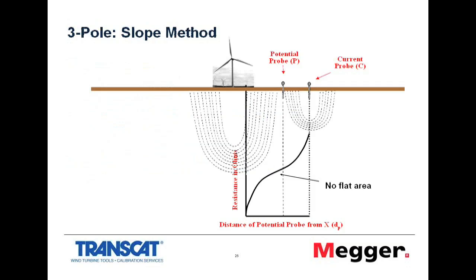If I look at a single wind turbine, I can see that the sort of spacing I would require is going to be in the order of something like 425 feet. A 2 megawatt turbine earth system is approximately, across the biggest dimension of the earth system, 75 foot across. And with that kind of size earth system, I need to have the current probe about 425 feet away to be able to see a flat. That's taking into account variation in the soil makeup and the moisture content, which can vary throughout the year, and we have to take into account those factors when we take that measurement. Effectively, you're looking at quite long lead sets.